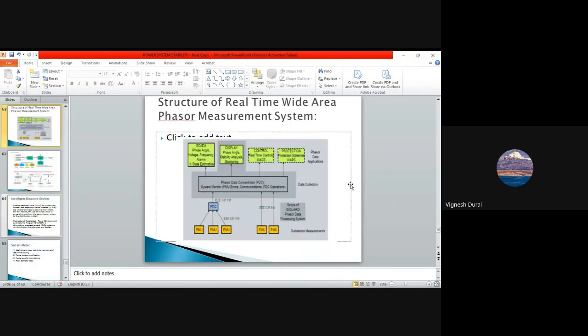Next, PMUs. These PMUs from the field level go to a data concentrator, which is again a PMU. This PMU will go to a master PMU, where they have application programs, where state estimators will raise an alarm if some dispatch is wrong. It will monitor. It can be integrated with SCADA also. You can see all the real-time data also, and if something goes wrong, it can protect immediately. It can give trip signals at field level, so that your system is protected from abnormalities.